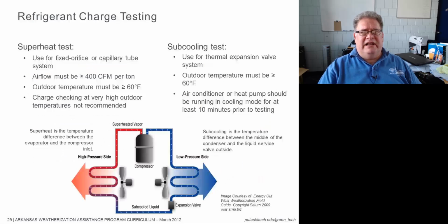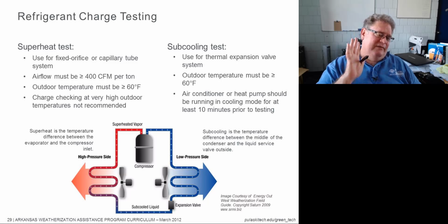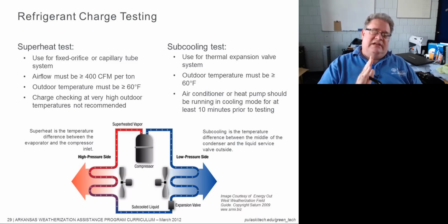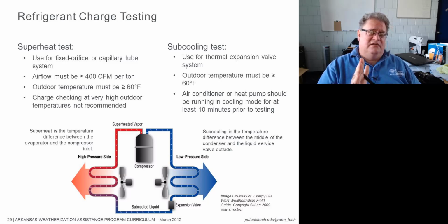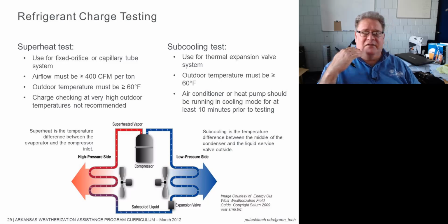Refrigerant charge testing, I'm not going to get too deeply into it, but generally on a superheat test, you're going to use this for a fixed orifice or a capillary tube system. Your airflow is going to have to be at least equal to or greater than 400 CFM per ton. Now that is a rule of thumb and I don't like it. However, it's still being used quite a bit in procedural tests, okay? If you don't have the airflow, you're not going to get the superheat that you need, all right? Then you're not going to check your charging at a very high outdoor temperature. If you're in Phoenix or something and you guys are seeing temperatures over 100 degrees, that's probably too high, okay?